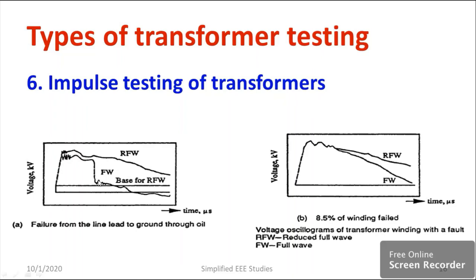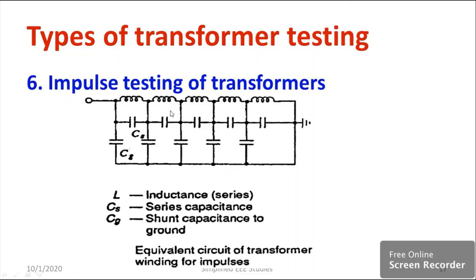You can apply either reduced full wave or full wave — if you find any sudden droop, you know there is a problem in the transformer insulation — there is a short circuit. This winding diagram is helpful for conducting the testing. It is the equivalent circuit of the transformer winding, required for conducting impulse testing. Where L stands for series inductance, Cs stands for series capacitance, and Cg stands for shunt capacitance to the ground.